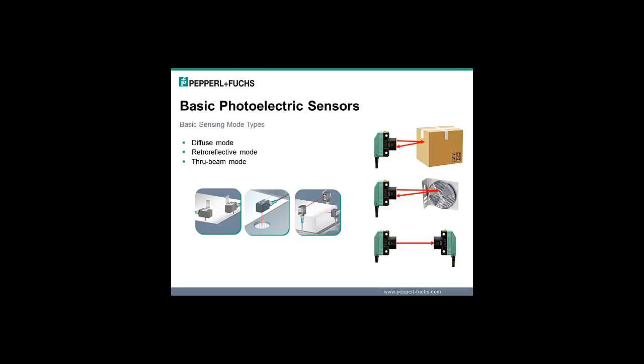One sensing mode type is diffuse mode. In diffuse mode, a sensor emits light that is reflected at various angles by an object back to the sensor's receiver. Another sensing mode type is retroreflective mode, in which a sensor emits light that is returned back to the sensor by a retroreflector, and when an object obstructs the light beam, the sensor's output changes state. The last basic sensing mode is through beam mode, in which the sensor's transmitter and receiver are in two different housings and an object obstructs the beam to cause the output to change state.